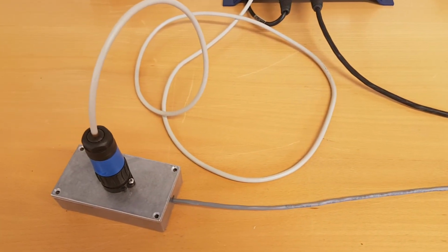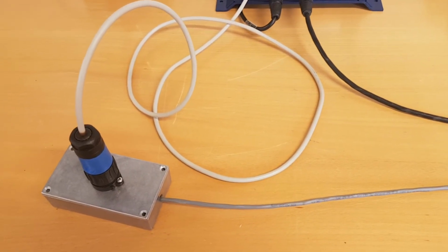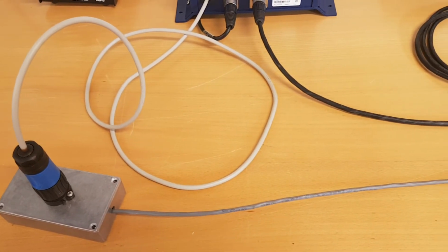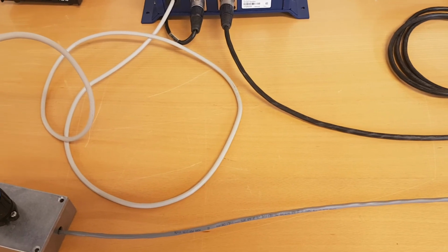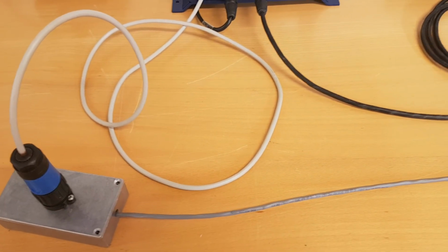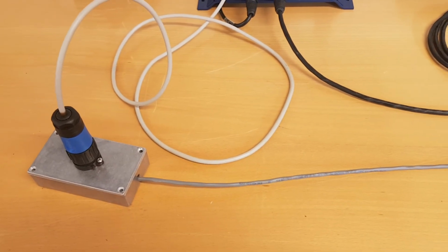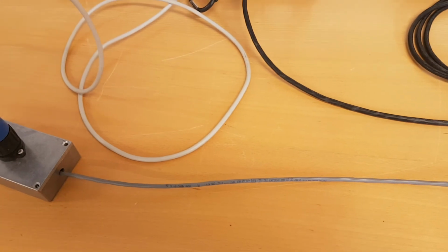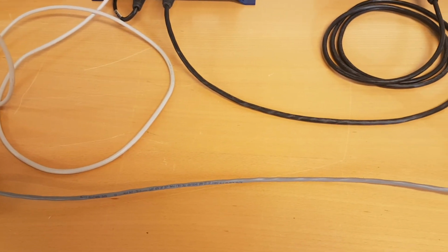Signal cables normally have pairs of conductors, and one pair is two wires which are twisted around each other, and it's important to use that one single pair for this communication. The other pairs, put them aside and leave them for spare or for other use, but use only one pair of signal conductors in a signal cable.